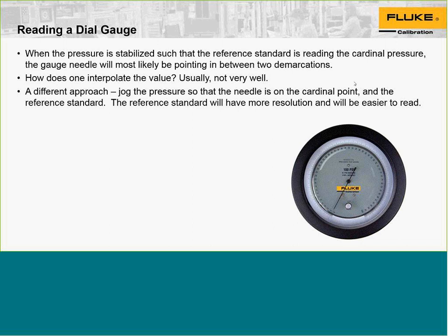Some in practice do not follow this procedure. It's an example of working it, and what the dial gauge is reading immediately after the pressure is changed versus allowing it to stabilize at the pressure. That's dependent upon the application. For the application of most dial gauges, this is an acceptable and common practice.